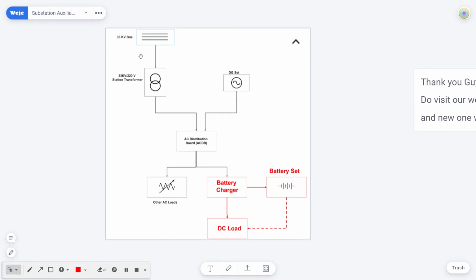So if you see the start, this is our 33 kV bus in the substation, and connected to that bus is a station auxiliary transformer, which transforms 33 kV into 220 volt, and which is then fed to the AC distribution board, ACDB.